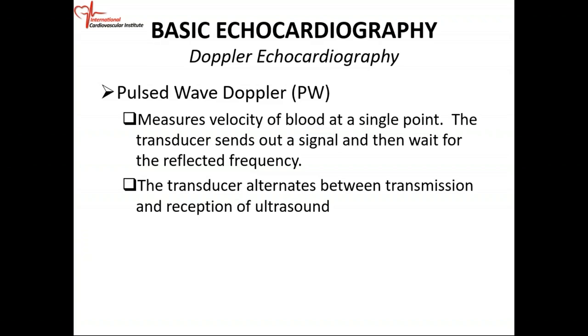The transducer sends out a signal and then waits for that signal to be reflected backwards. Because it's doing this, it can only measure low velocity movements. The transducer or probe itself is alternating between sending out signals and receiving the signal — it alternates between the transmission and the reception of ultrasound.